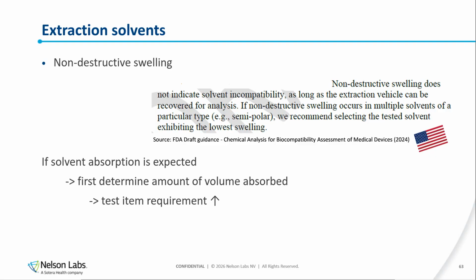What you will have to do is check how much solvent is absorbed. And of course, this means that you will need to test this separately before the rest of your study, meaning that the item requirement goes up. So if solvent absorption is expected, it's best to always do this upfront. Otherwise, you will start to do an exhaustive extraction, for example, and all the volume goes away, and then you can restart again.